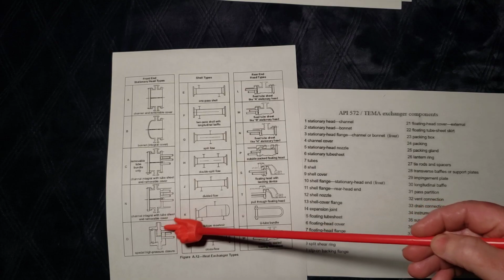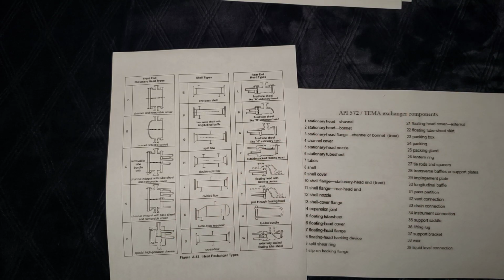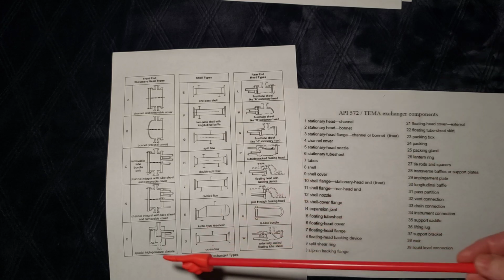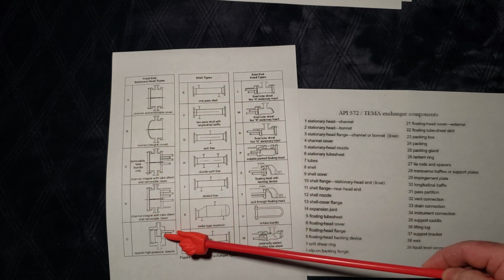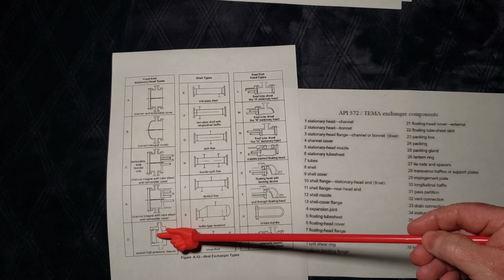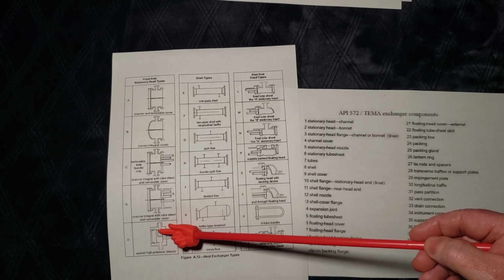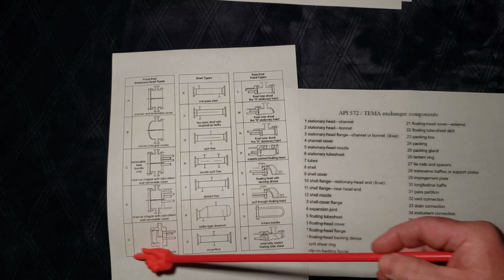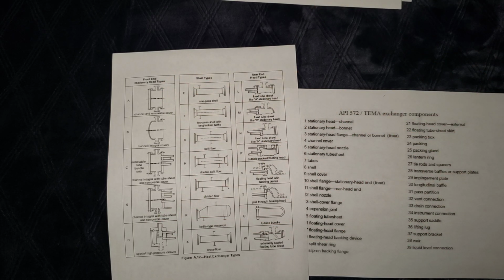Those exchangers with that delta type cover were very, very large. They were, goodness, over 4 foot diameter and over 2 foot thick for the cover. Had an Acme type thread that threaded the unstayed cover into place. But the neat thing about that is even 25, 30 years later, the best way to describe those would be a D-type front head configuration that just happened to be manufactured in Kobe, Japan.